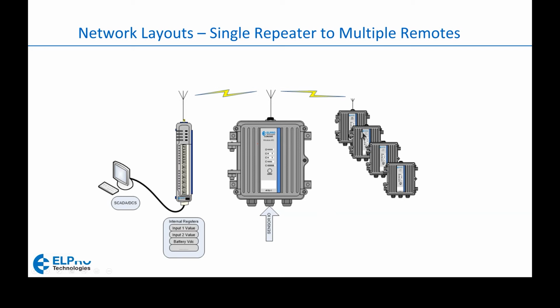And here we go. So these are remote sites, remote 415U2s going to a repeater 415U2. And of course, you can have some 4 to 20 milliamp signals going into this radio, so it can function as a remote site and as a repeater for these other locations. And then, of course, we shoot all this data back to the control room radio, where we would use either the 415U-2 or the 415U-E. And then these radios are capable of Modbus as well as DNP3 protocol. So we connect that to our SCADA system, and we can control everything remotely via radio system.